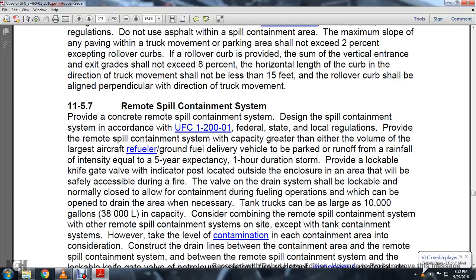Rollover curbs should not be less than 15 feet. The rollover curb should be aligned perpendicular to the direction of truck movement. 11-5.7, Remote Spill Containment System. Provide a concrete remote spill containment system, designed according to UFC 1-200-01, federal, state, and local regulations. Provide the remote spill containment system with capacity greater than either the volume of the largest aircraft refueler or ground fuel delivery vehicle load.